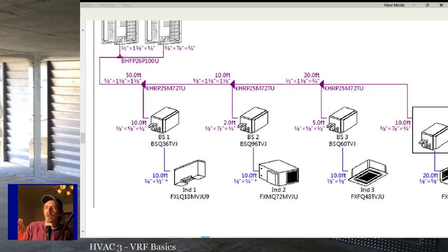Now, Richard brought up he did an install where there were too many 90s, and the pipe size ended up having to be upsized. Every 90 is equivalent feet, right? Every 90, I think, counts for 5 equivalent feet or something like that. So that needs to be taken into account too. Here's the rule with VRF piping. If you can avoid a 90, don't use a 90. Just use pipe. I don't care if it looks ugly. I don't care if it's not as pretty as you'd like it to be in the ceiling.